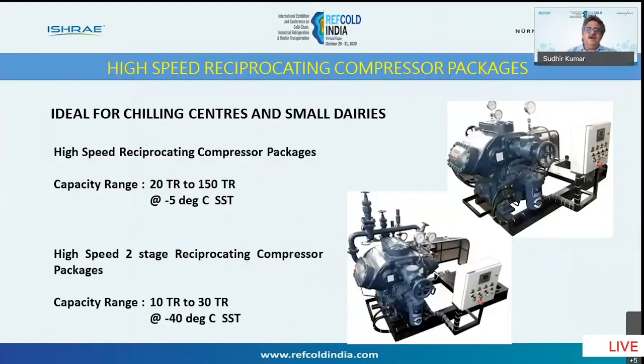Next comes the heart of the refrigeration system. So first we have selected the system configuration. After that we go in for compressors, which are the heart and which is the major power guzzler. So basically in a refrigeration plant, the major power is consumed by the compressors. So for small chilling centers and small dairies, people can use reciprocating compressors ranging from 20 TR, or rather 60 kilowatt, to almost 100 TR, even though it's mentioned 150. 100 TR is approximately about 350 kilowatt of refrigeration capacity.